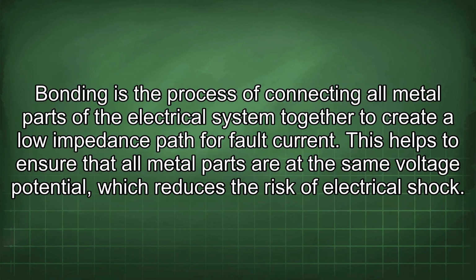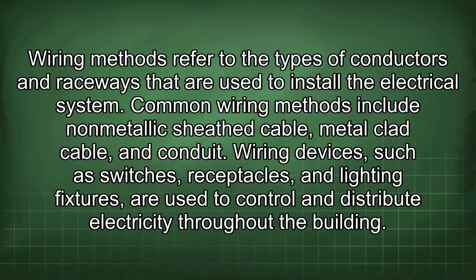Bonding is the process of connecting all metal parts of the electrical system together to create a low impedance path for fault current. This helps to ensure that all metal parts are at the same voltage potential, which reduces the risk of electrical shock. Wiring methods refer to the types of conductors and raceways that are used to install the electrical system. Common wiring methods include non-metallic sheath cable, metal-clad cable, and conduit.